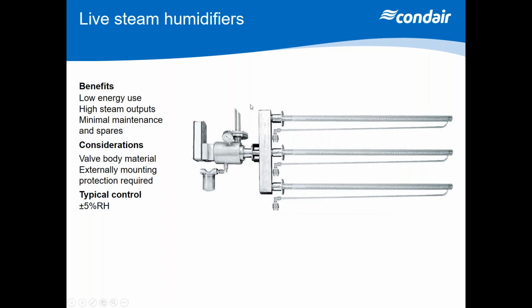You may, though, want to use that live steam, and you can do that by taking live steam through a pressure reducing valve, letting steam come into a valve body. In that valve body, condensate will be separated away, and in this case, taken away in an inverted bucket steam trap. And then steam, when the valve opens, will come into this header, to these tubes, and you can see you've got lots of little holes here that the steam's going to come out of, and then any condensate will be taken away through this little thermal trap and back into the condensate system. Low energy use, you're just utilizing an existing steam supply. High steam outputs, they start at 5 and they go up to almost 1,000 kilos an hour for these units. The only thing you really need to consider is whether clean steam is required. If clean steam is required, this valve body must be made of stainless steel, whereas as a standard, it will be supplied as cast iron.